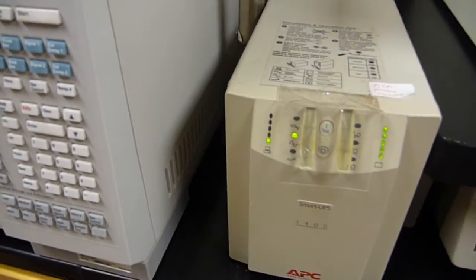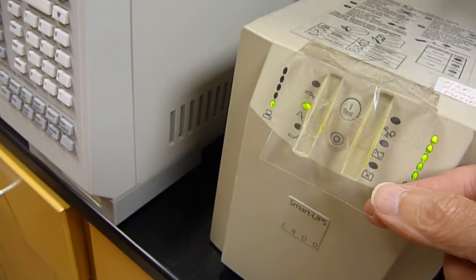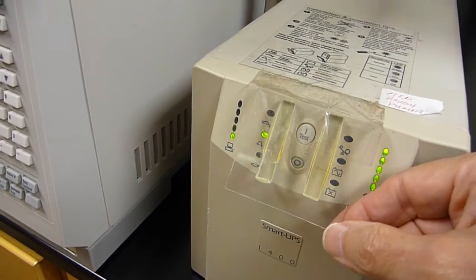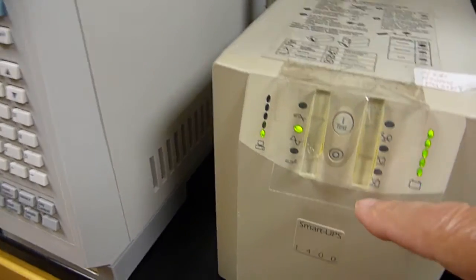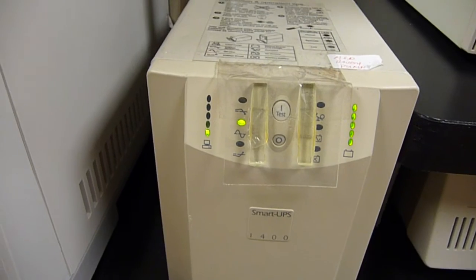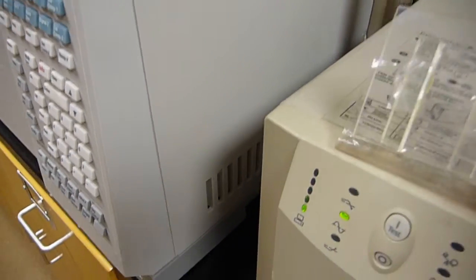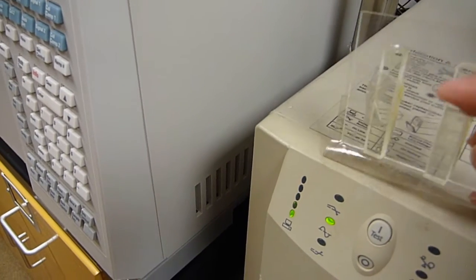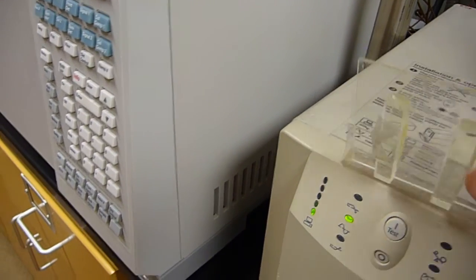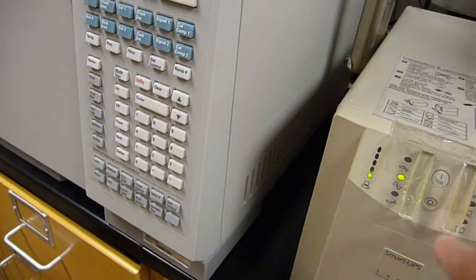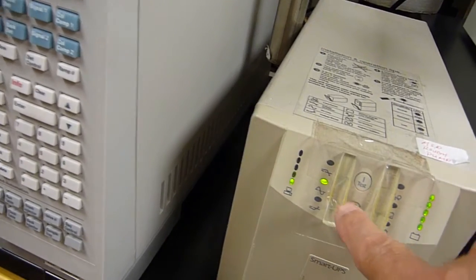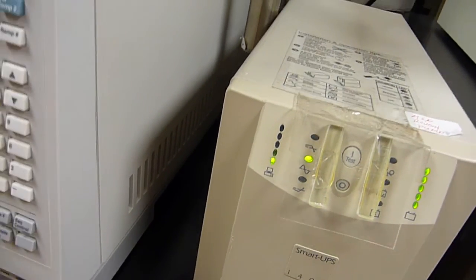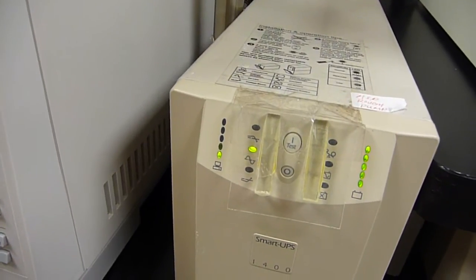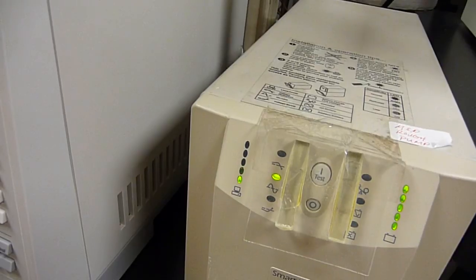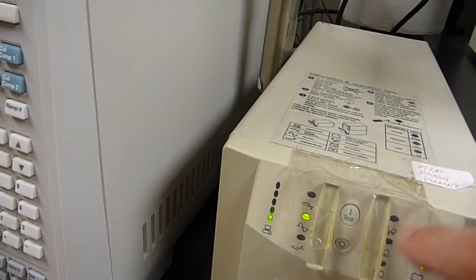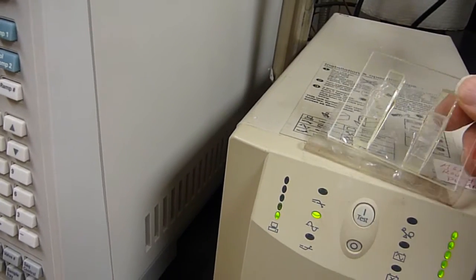If you do go down the road of having UPSs, make sure it takes a positive action on somebody's part in order to turn off the UPS. Inadvertent turning off of the UPS is something you don't want. So here we just make covers out of plexiglass with a couple of strips of plexiglass epoxied onto it, and then just use sealing tape. Now if somebody wants to hit that off button, they can't do it. In today's devil-may-care culture, people sometimes will inadvertently hit the off button. This way, it's a positive action that somebody has to lift and then push.